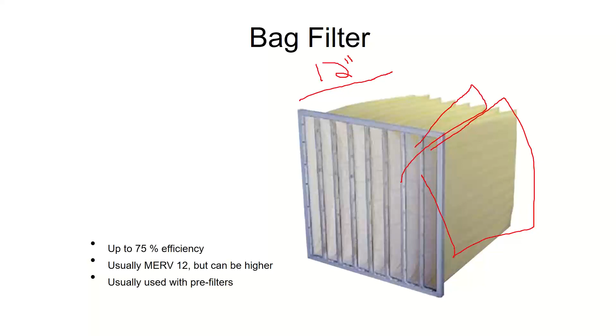You can't go throwing that in your furnace at home or even on a rooftop unit. It's got to be an air handler designed for that amount of space. But it does pretty good if you're trying to prevent bypass around the filter. Because if I put a bunch of these filters in, say 5 of them in a row, and the next one's right next to it, how tight is that gap? Not very tight, and if there's a gap there, air is going to leak by it.